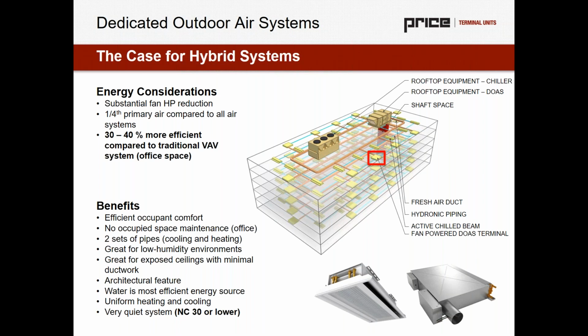So we're seeing the same fan horsepower reduction on the rooftop unit. We're seeing fan horsepower reduction even with the inclusion of all of the zone fans. We're still seeing far less energy consumption just because the volume of air being moved is less for a shorter distance. We're still seeing that quarter of primary air compared to all air systems, and we're still seeing that huge increase in efficiency. The benefits still exist as well.